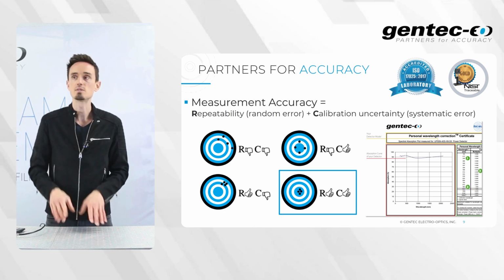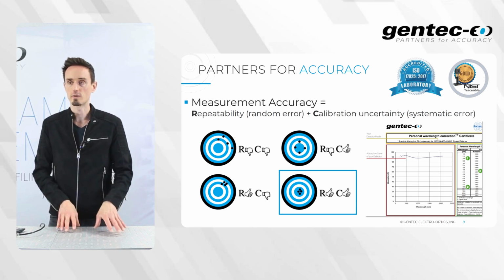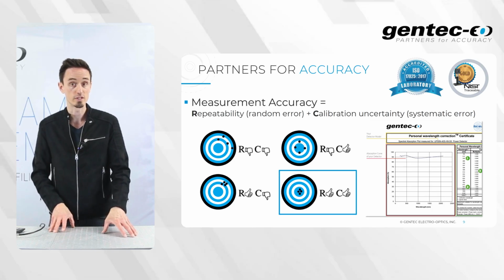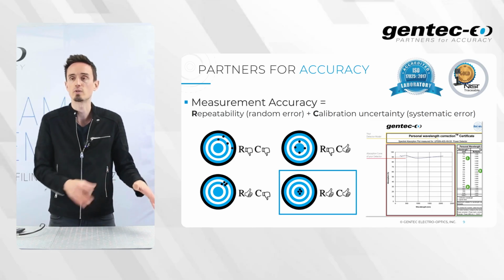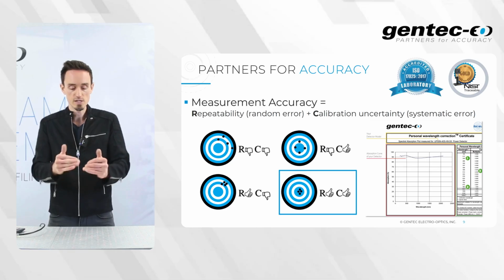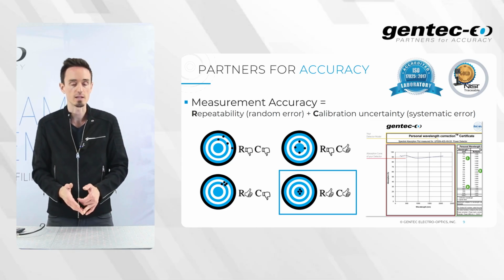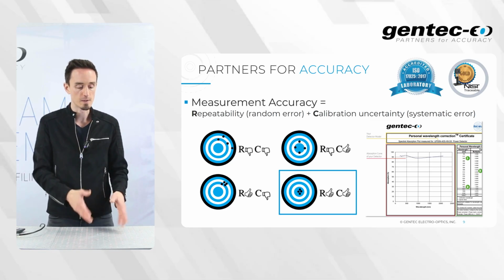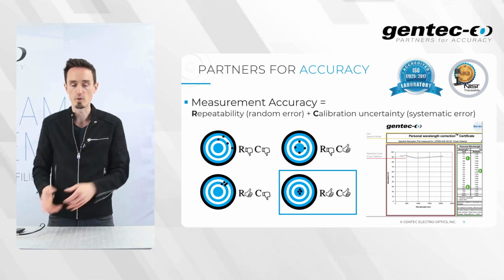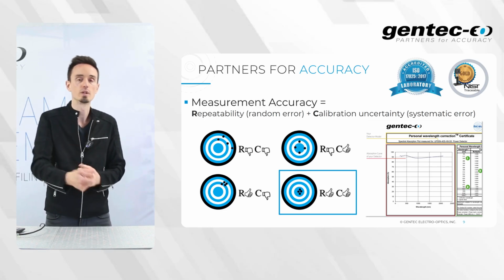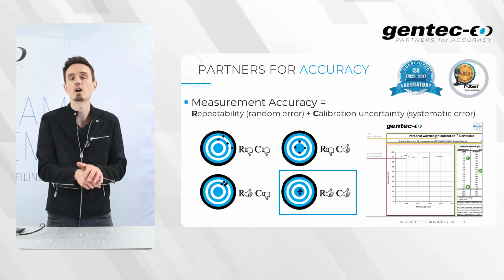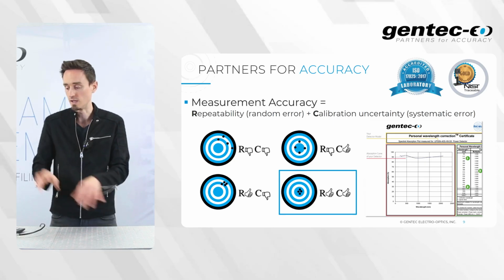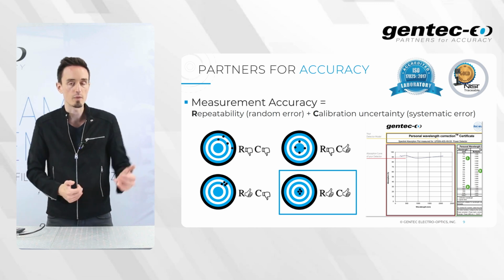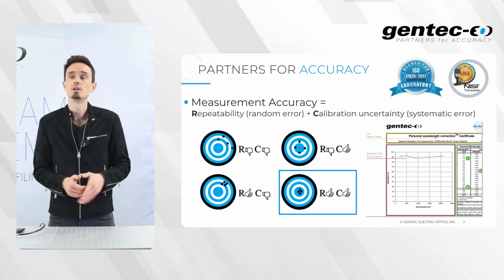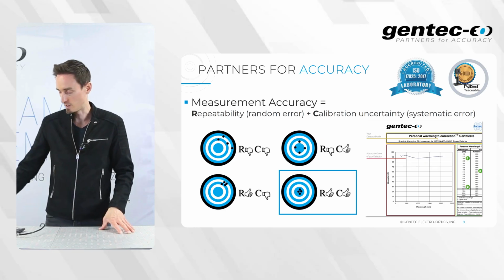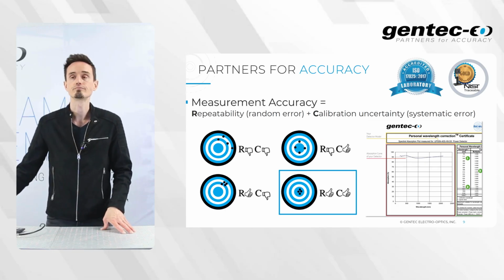On the right side of the slide, you see what we call the Personal Wavelength Correction Certificate, which is a document that we provide for every detector. We do measure the absorption of every detector that we offer. This is to decrease the calibration uncertainty and to be sure that we use the proper absorption value. Using a NIST traceable spectral photometer, we measure the absorption of all the detectors and we load those calibration coefficients in the EEPROM, the electronics of those detectors. So when you enter your wavelength in your control interface, it will retrieve the proper calibration and the proper absorption value to derive a more accurate measurement, with the uncertainty as low as possible.